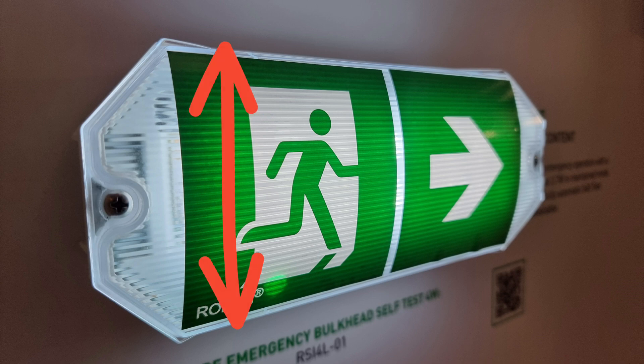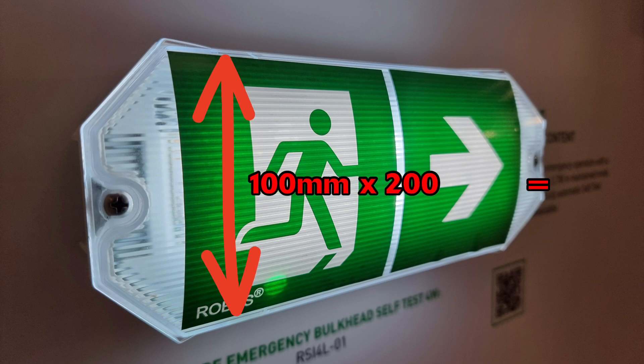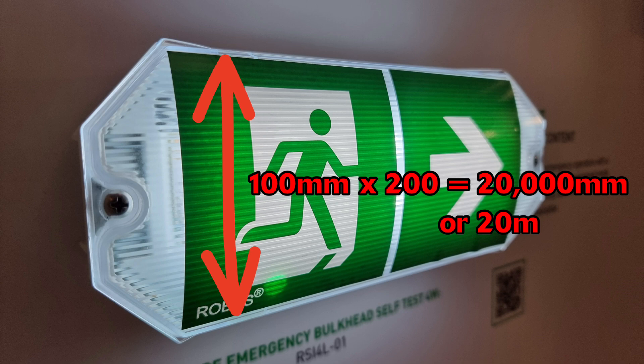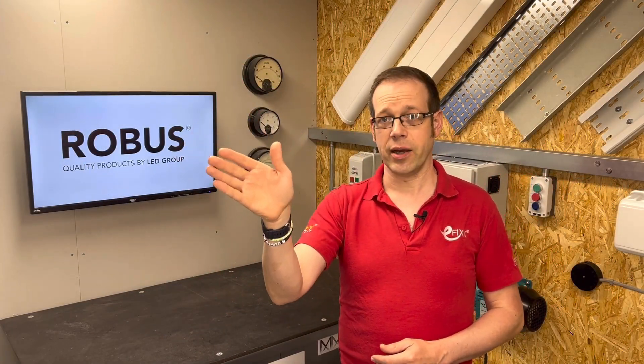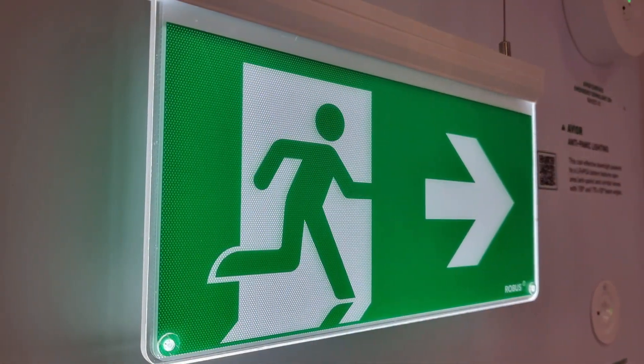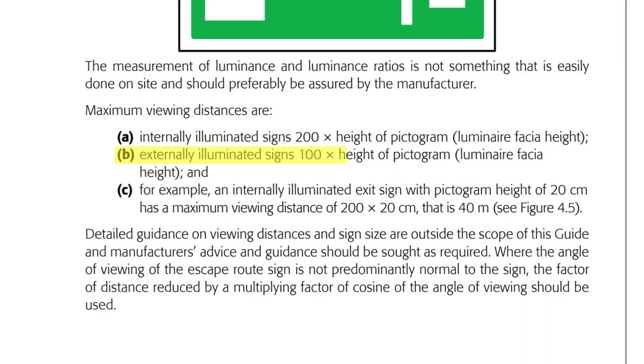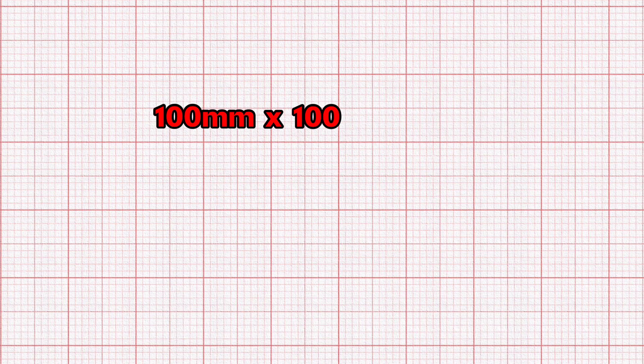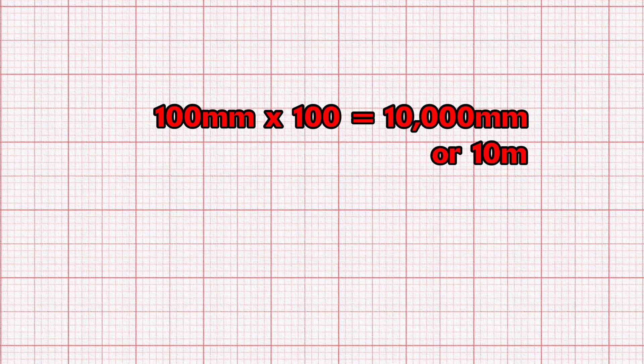On this Robus fitting the sign is 100mm high; multiplying by 200 gives 20,000mm or 20 metres — the maximum distance at which the sign can be seen and legibly understood as giving a direction to safety. If the fitting is at the end of a long corridor, it may be necessary to either install a fitting with a taller pictogram or add another sign further along. For externally illuminated signs — lit from a separate emergency fitting — the distance is reduced to 100 times the height of the pictogram, giving a viewing distance of 10,000mm or 10 metres: a smaller range but entirely acceptable within that limitation.